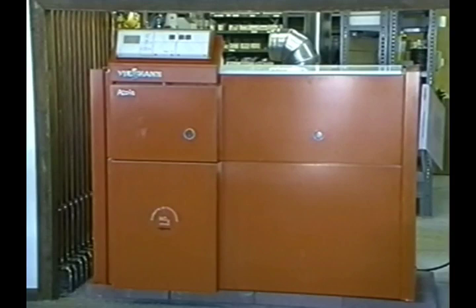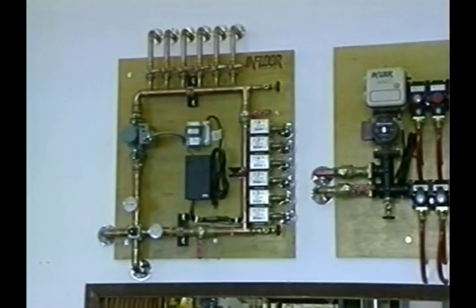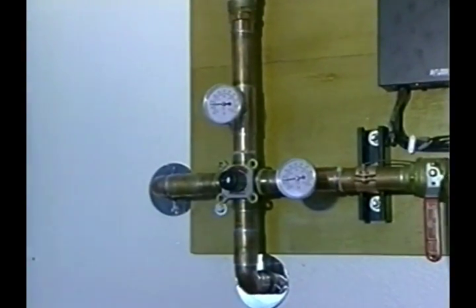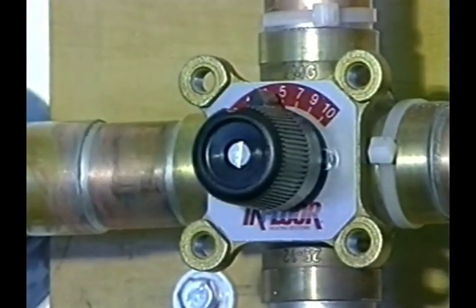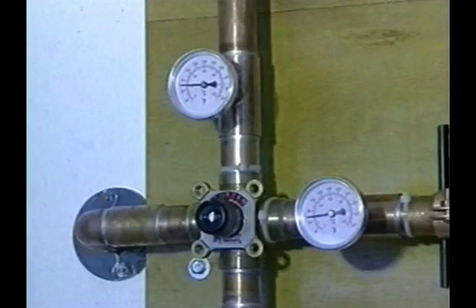At this point, we have up to 180-degree water. A radiant floor requires a maximum of 140-degree water. It's necessary to provide some way to temper our water going into the radiant floor area. A four-way mixing valve does this job very well. It tempers the water by mixing return water from the floor area with supply water from the boiler. A four-way mixing valve assures proper flows in the radiant floor and the boiler. The mixing valve may be manually adjusted to provide the proper temperature into your in-floor heating area.